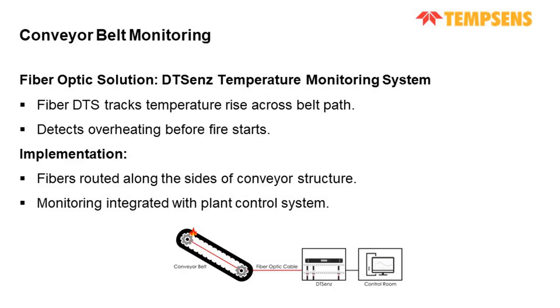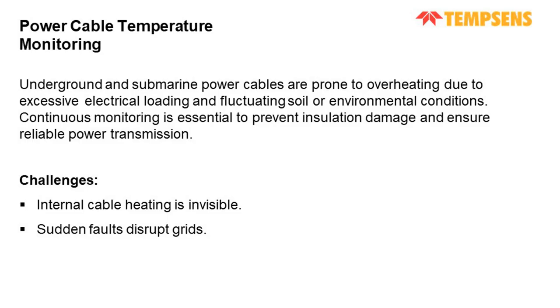So the fiber optic solution in this case would be a DTS temperature monitoring system, as it is suitable for long conveyor belts and it can measure temperature continuously over the whole profile of the conveyor belts. So using DTS, we can lay fibers along the length of the conveyor structure to detect localized heating. And these sensors provide continuous temperature profiles along thousands of meters. And when a bearing starts to fail, it heats up, and the fiber system immediately flags that zone. A maintenance team can be dispatched before a serious failure occurs, and this predictive capability ensures uninterrupted operation and reduces maintenance costs significantly. Our next application is power cable temperature monitoring.